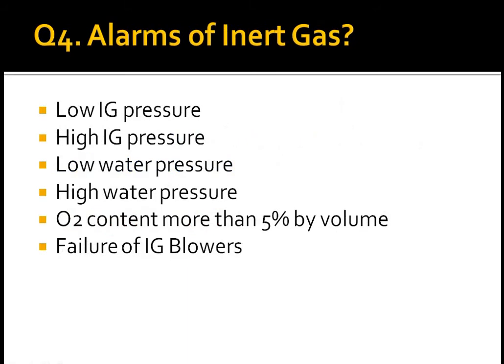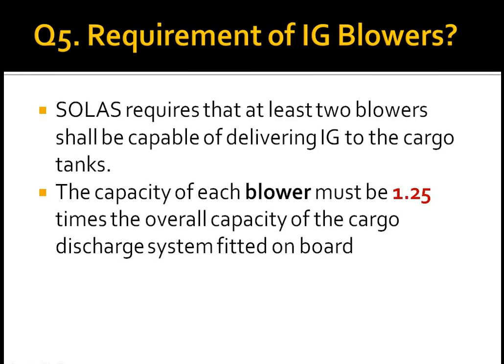Question 4: alarms of the inert gas system. These include low IG pressure, high IG pressure, low water pressure, high water pressure, oxygen content more than 5% by volume, and failure of the IG blower.